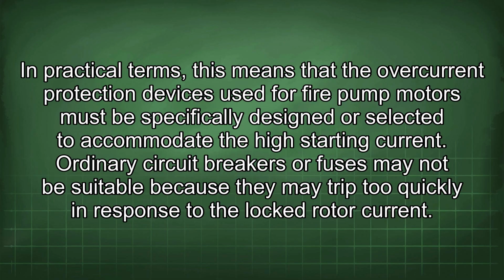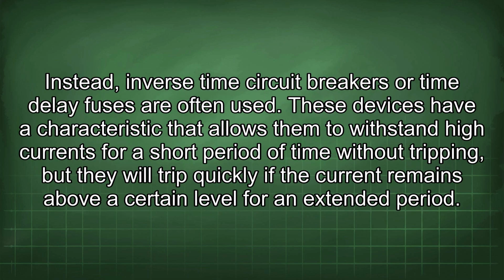In practical terms, this means that the overcurrent protection devices used for fire pump motors must be specifically designed or selected to accommodate the high starting current. Ordinary circuit breakers or fuses may not be suitable because they may trip too quickly in response to the locked rotor current. Instead, inverse time circuit breakers or time delay fuses are often used. These devices have a characteristic that allows them to withstand high currents for a short period of time without tripping, but they will trip quickly if the current remains above a certain level for an extended period.